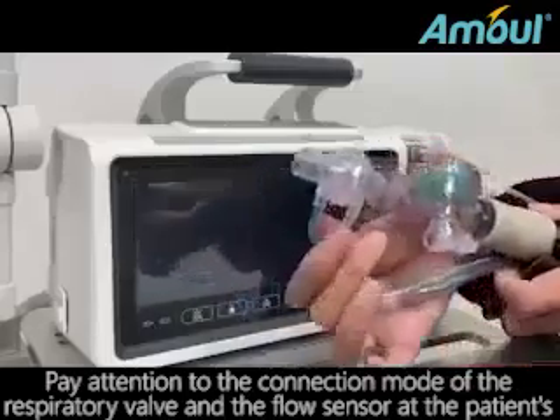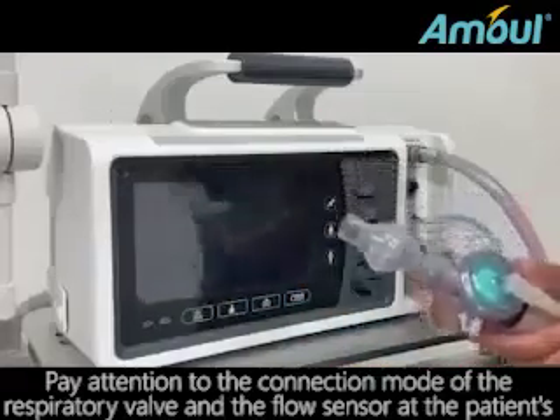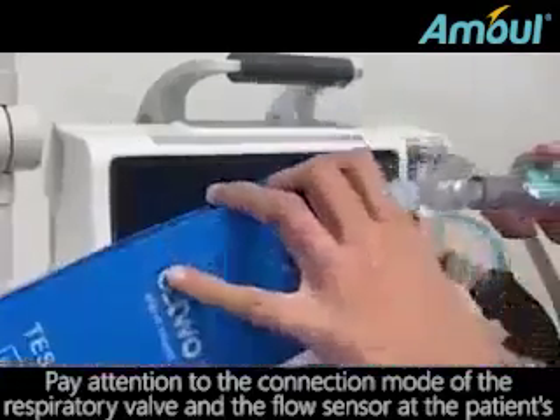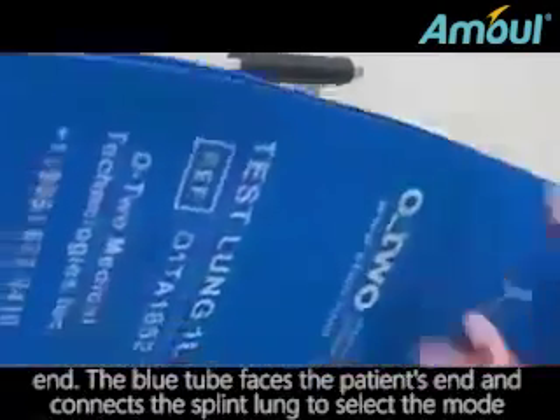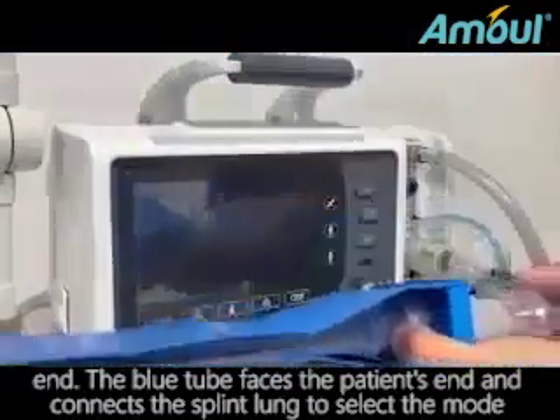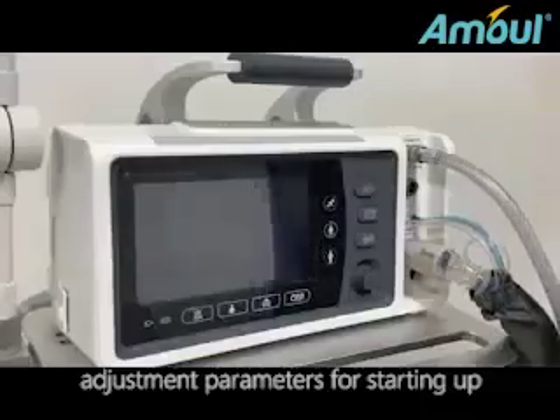Pay attention to the connection mode of the respiratory valve and the flow sensor at the patient's end. The blue tube faces the patient's end, and connect the test lung to select the mode. Adjust parameters for starting up.